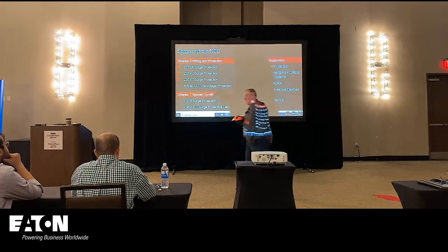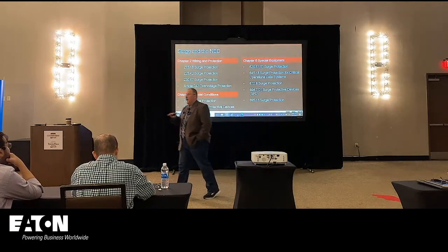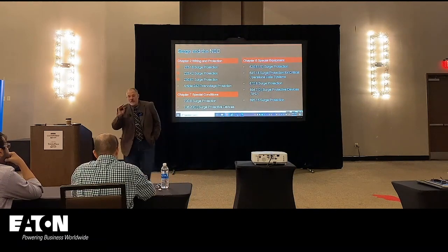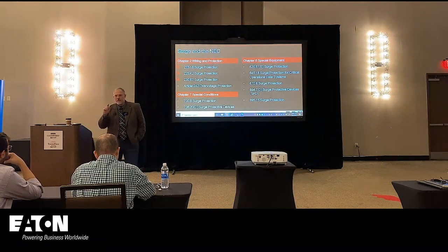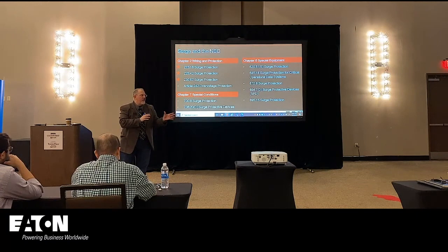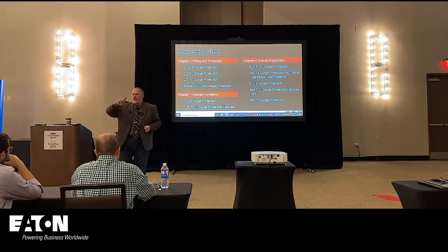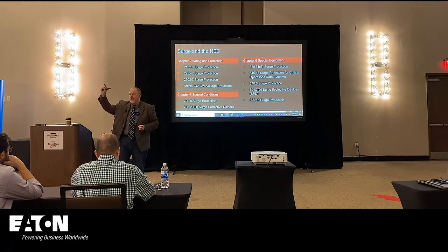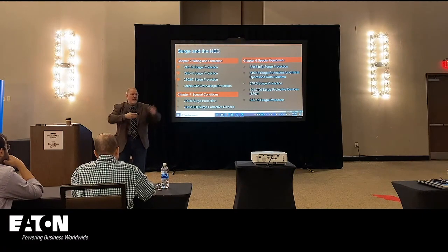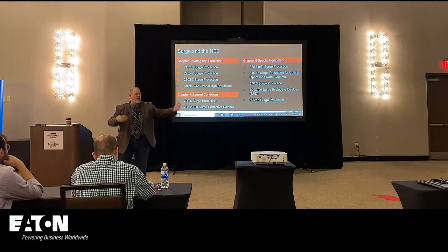And then this cycle, what we had to clean up, there was a realization on panel 10 that sometimes, we had it in Article 230 for services for dwelling units. But then we said, well, wait a second, what happens if the service is out at the road? Because in many cases, the service is out at the road, and then we have what? An outside feeder that comes to the structure. We don't want surge out at the road. We want surge on the structure, right?